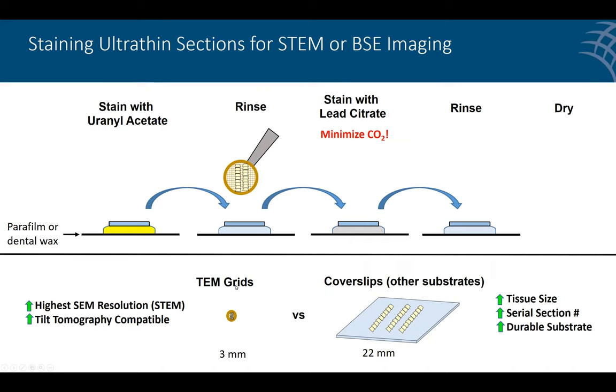You may wonder when to use TEM grids versus coverslips. TEM grids may be fine if you're already comfortable with them — STEM gives the highest resolution biological imaging on an SEM, and you can do tilt tomography at many angles. Coverslips are great for much bigger sizes — a TEM grid is 3 mm, but a coverslip can be 22 mm or even semiconductor wafers. You can get a lot more serial sections on a large surface, making management of hundreds of slices easier. Also, the thin membrane on grids can break and you lose data, while coverslips are more robust for archiving.